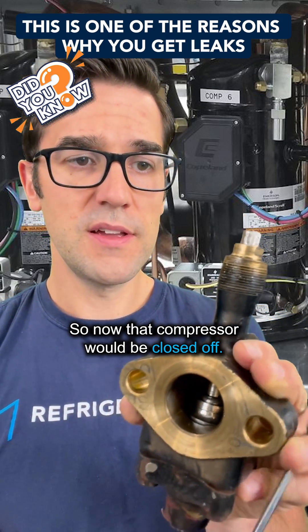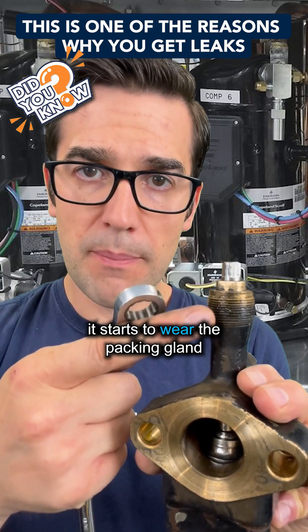Just say you're pumping down the compressor — we front seat it. So now that compressor would be closed off. What you want to do is loosen your packing, because every time you open and close this and you don't loosen and tighten the packing, it starts to wear the packing gland.